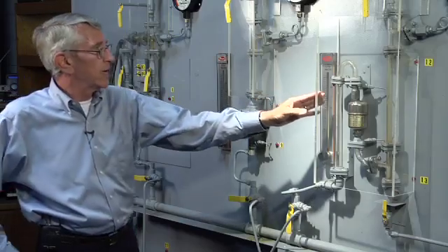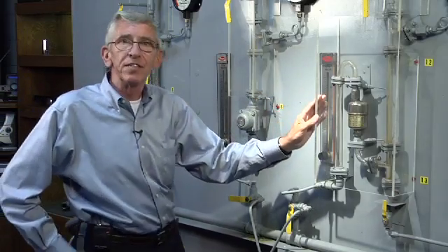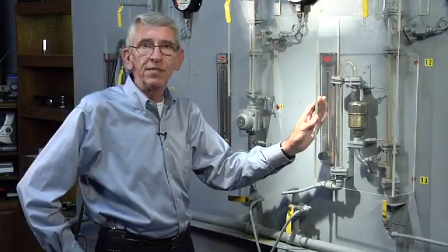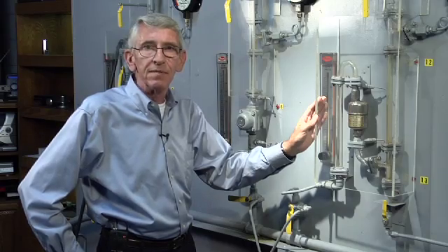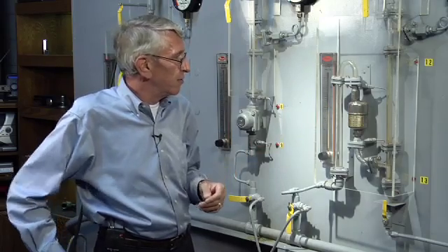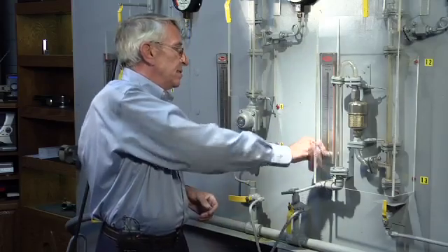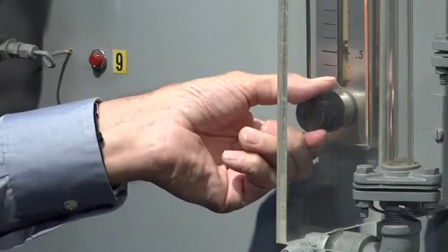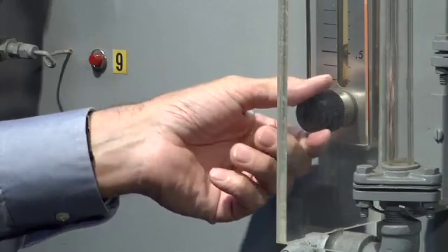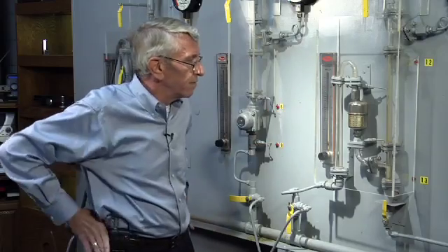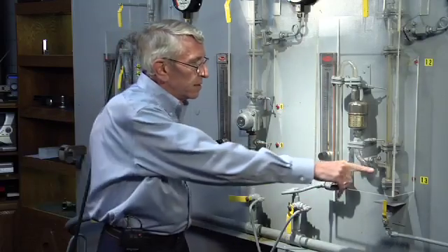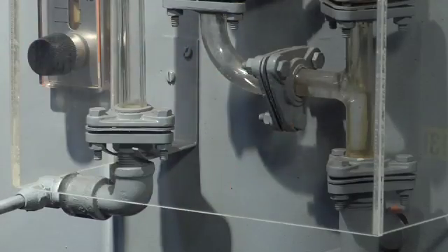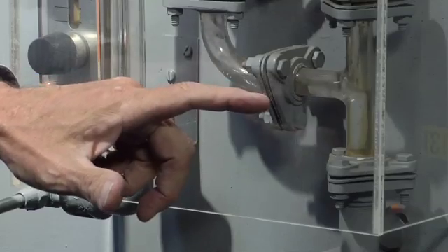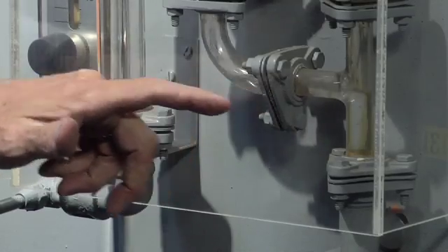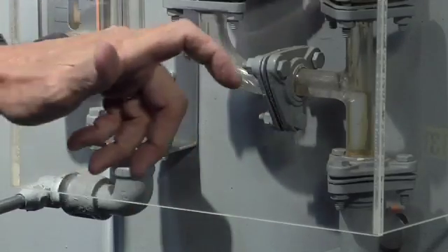The inverted bucket trap, on the other hand, operates on the difference in density between the steam and the condensate. So temperature has no effect. If I increase the load to the heat exchanger being drained by the inverted bucket trap, you'll note that the condensate level never gets above the level of the inlet tubing going to the trap. I have no backup toward the heat exchanger at all.